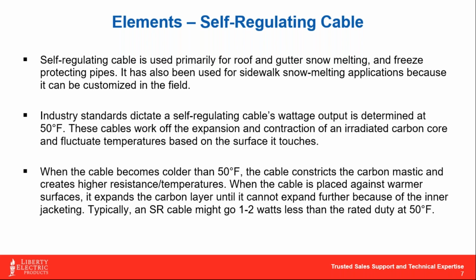A self-regulating cable works off of expansion and contraction. The entire magic of how this cable works is based on the surface temperature of whatever it's up against. When you warm things up, put them against a warm surface, most materials want to expand when heated. So the inner core of this cable actually expands when heated, pushing the bus wires further apart, which reduces wattage output.